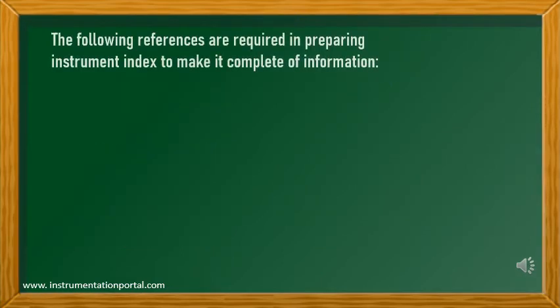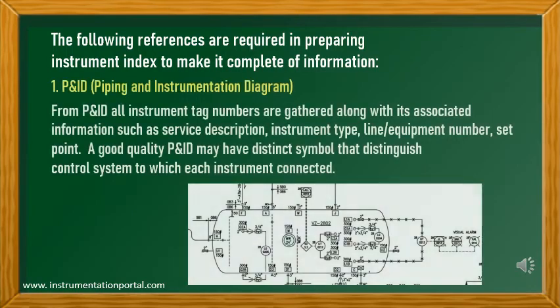The following references are required in preparing the instrument index to make it complete. First, P&ID or Piping and Instrumentation Diagram. From P&ID, all instrument tag numbers are gathered along with associated information such as service description, instrument type, line number or equipment number, and set point. A good quality P&ID may have distinct symbols that distinguish the control system to which each instrument is connected.